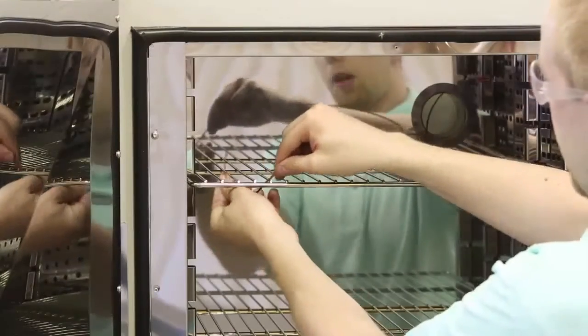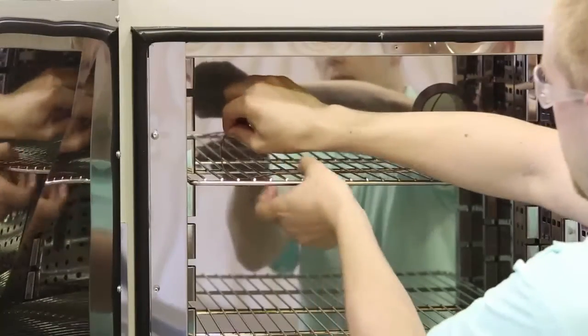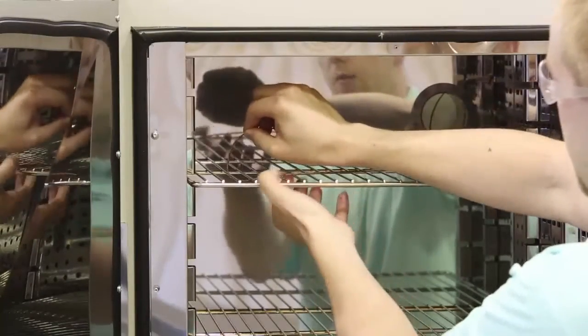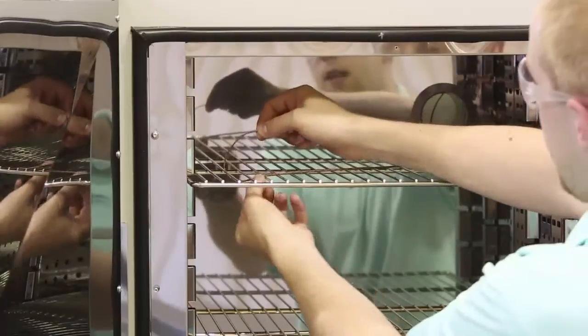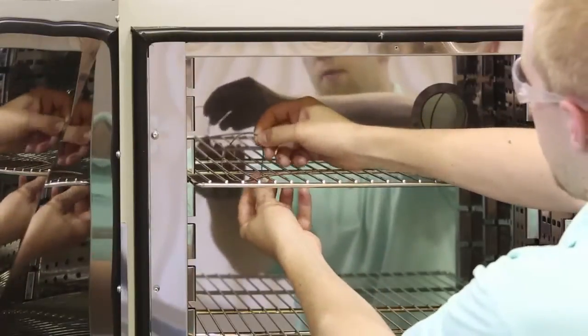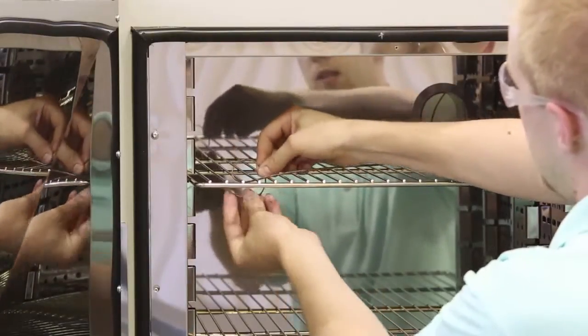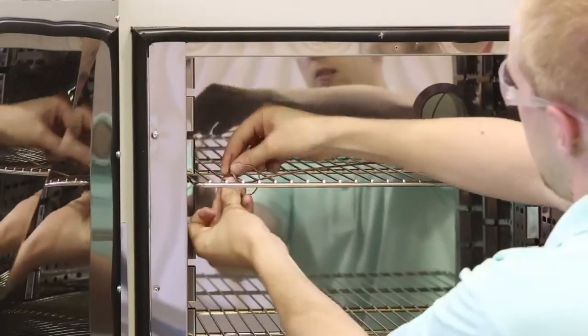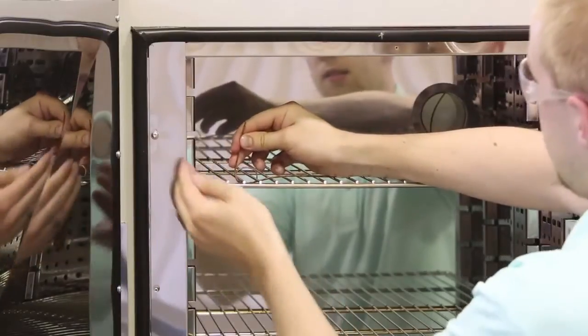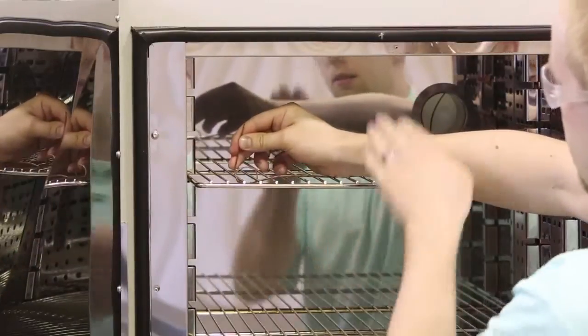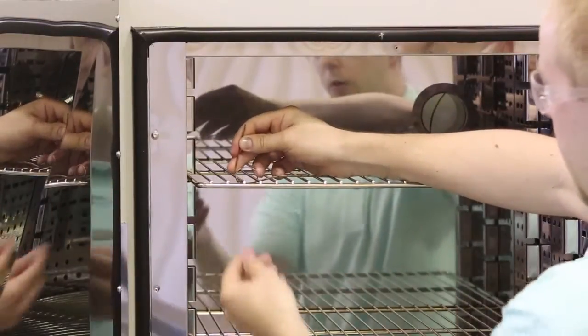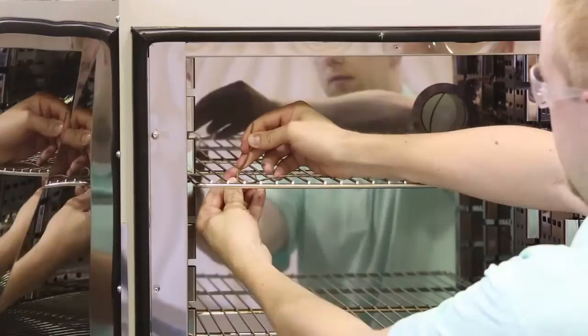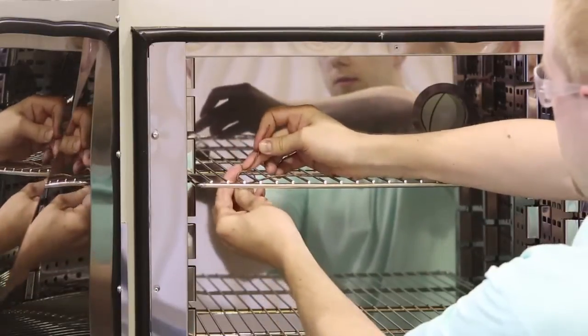Inside the oven, position a thermocouple in each of the eight corners of the oven. Loosely wrap the thermocouple around the oven rack and position the tip of the thermocouple about three inches away from any oven surface. Mechanical stress can cause a shift in the calibration of the thermocouple, so be sure to avoid any sharp bends.